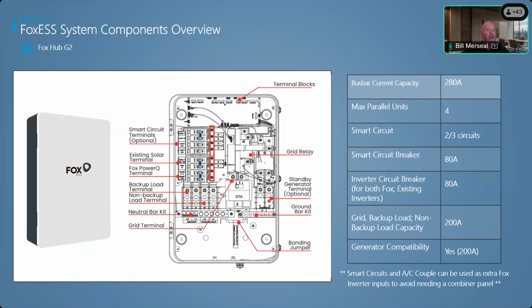Once you go to the grid terminal, the power goes through the system, through the smart circuits, existing terminal, etc. So if that power was to be lost, that breaker right here would go into the off position. And when that grid relay flips to the off position, we are now in islanding mode. So what's going to happen is your DC takes over on this whole side. So your solar input, either from existing solar, from AC connections, or from the Fox system, will go right onto that left side and it'll run like an island. So that's how the islanding function works, which is why these batteries are really important if, for whatever reason, you lose power either from solar or from the grid. So that's going to be very important.